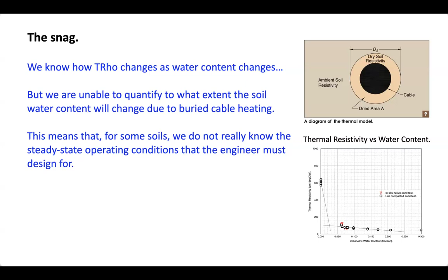We know how the thermal resistivity changes as the water content changes, because that's what's on the graph there. But we are unable to quantify to what extent the soil water content will change due to the heating. So we know what the thermal resistivity will be at a given water content. We just don't know what the water content will actually be under operating conditions. And so this means that for some soils, we do not really know the steady state conditions that the engineer must design for. This is the snag.